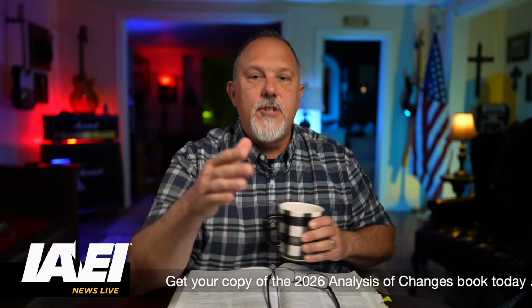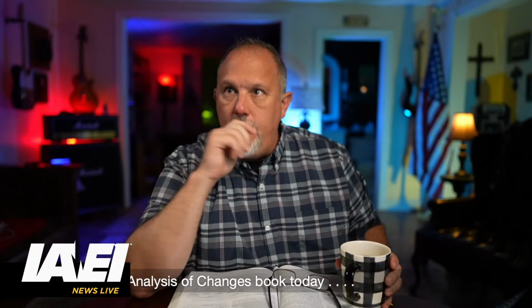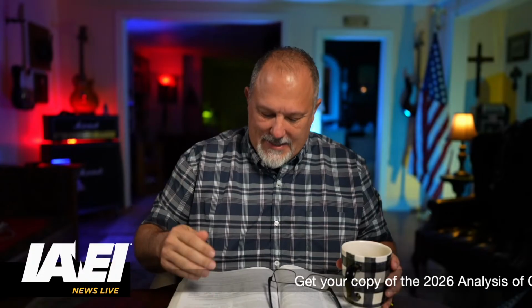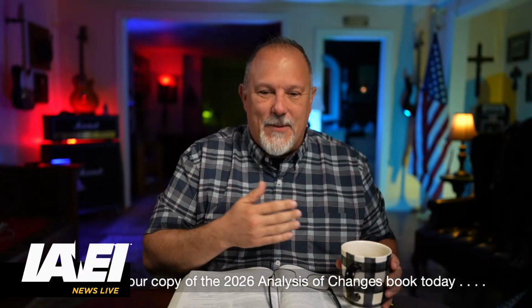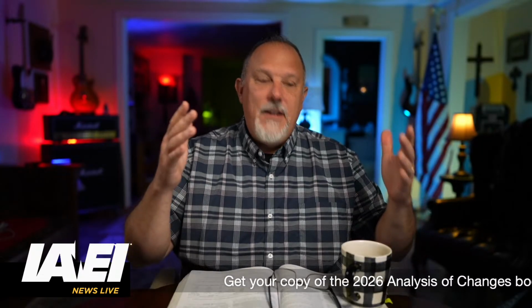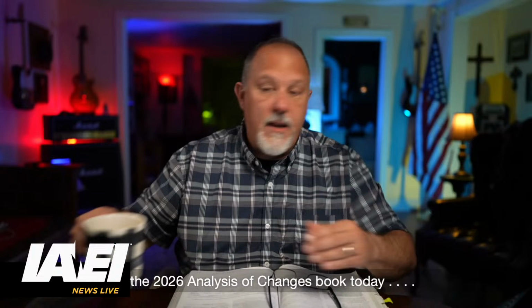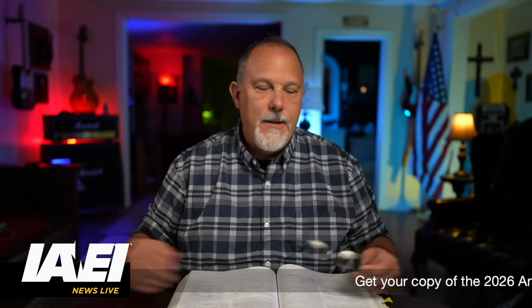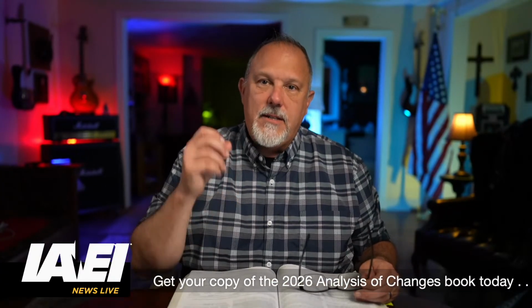Then I learned quickly that when you get into a 4160 to 480, I was initially confused, thinking, well, for the 480 volt side, do I go to table B? And for the 4160 side, do I go to table A? Or do I stay in table A because one side of this transformer is medium voltage, so I treat the entire thing that way, and that's the right answer, right? So if one side of this transformer is greater than 1,000 volts AC, then you're into medium voltage, and regardless of what that secondary could be, 208 volts, whatever it is, it doesn't matter. It's still a medium voltage transformer.